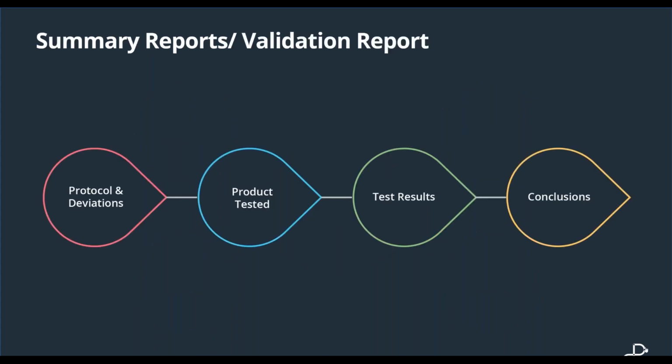So in terms of your final summary reporting, validation reporting, depending on what you're calling it, will depend slightly on whether you're doing a US submission or a European submission. But your human factors engineering report included in your pre-market submission should be providing information about your device use, safety and effectiveness in a summary format.